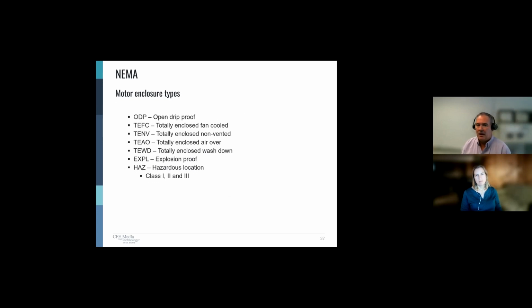All right, now where are we going to put our motor? What kind of enclosure does it need to have? Is it going to be a wet environment? Maybe we want open drip proof. Does it need to be fan cooled? Can it be fan cooled? It'll probably run a little better if we keep it a little cooler. So maybe we use totally enclosed fan cooled.